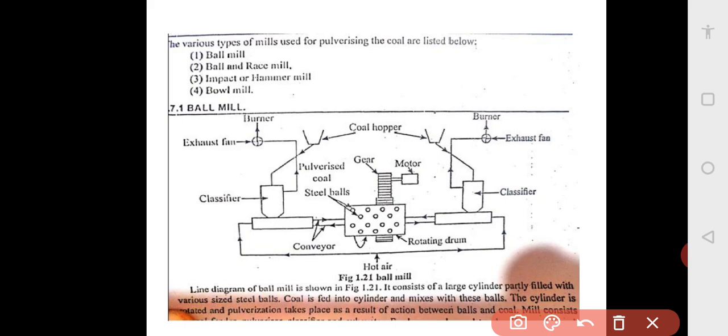Because the lump coal is there and the steel balls are rotating, the steel balls hit the coal particles. Over time, the coal particles become pulverized. This pulverized coal goes back to the classifier. Hot air is supplied from the bottom, comes to the classifier, and the pulverized coal is taken by the classifier and sent to the burner.